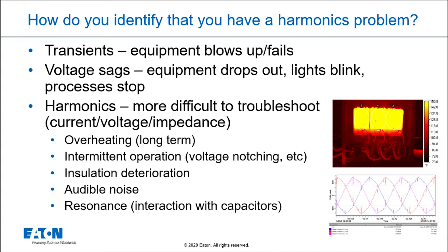If I have insulation deterioration, consider this: if you had a transformer and you were trying to identify whether it had a harmonics issue or a transient issue, look at the insulation. If it looked like it was baked in the oven for a year, that's probably a harmonics issue. If you have a single pinpoint failure on pretty new-looking varnish, that's probably a transient problem.